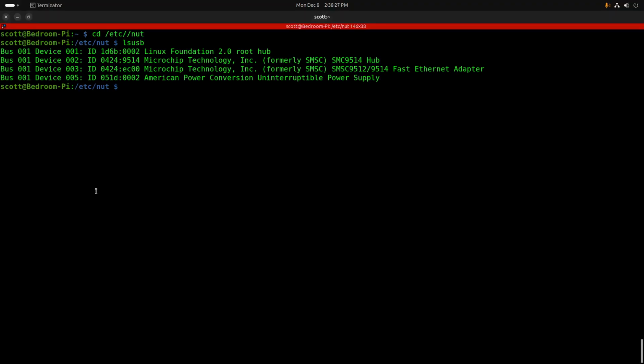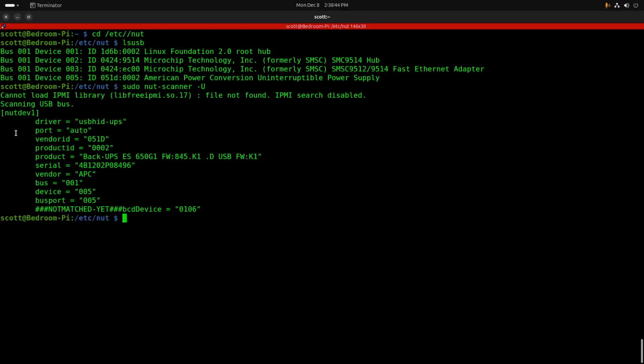One of the great things that the NUT software does is it provides this command called the NUT scanner. So here I'm doing a sudo nut-scanner -U to see the connected UPS units, and there it reads them out. So nutdev1 is just an arbitrary name it gave to this UPS device. We're going to change that later, and the driver is usbhid-ups, which is pretty much universal amongst any USB connected UPS unit.